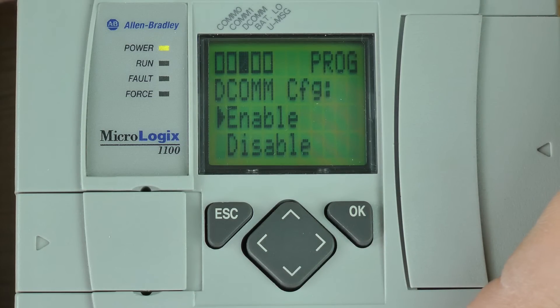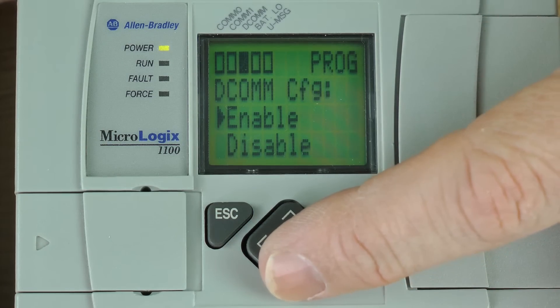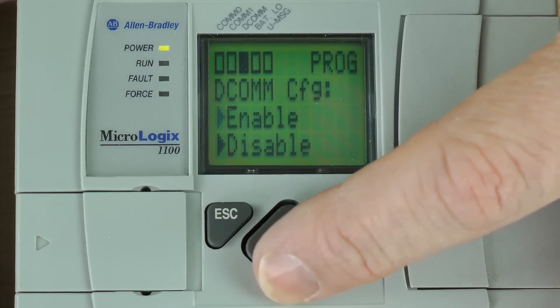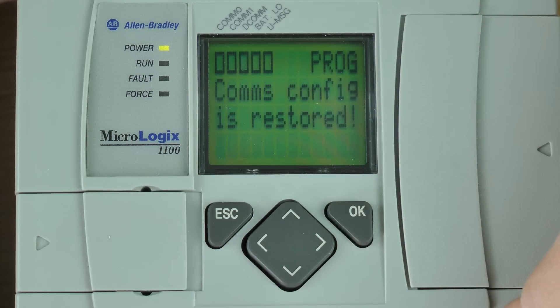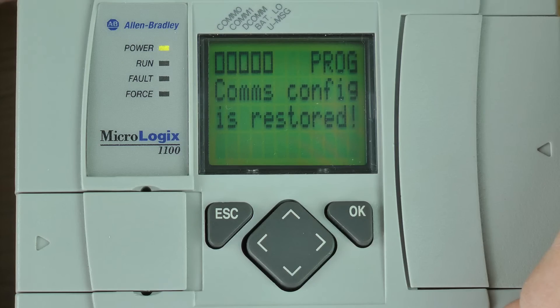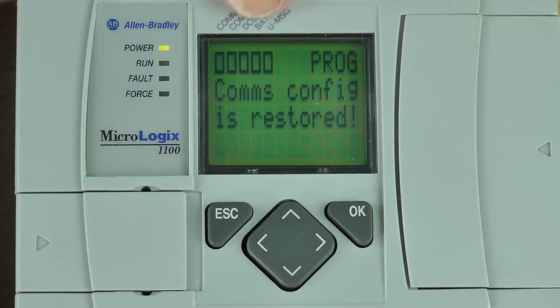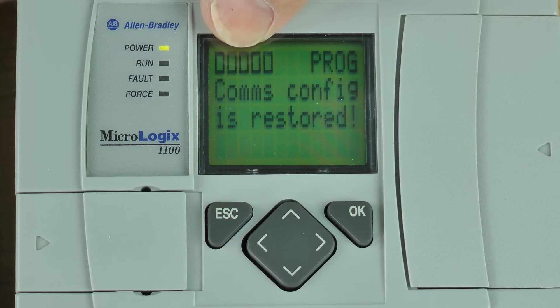I'm going to press the down arrow button once and okay to disable DCOM. Now you see a message saying comms config is restored. You'll also notice the middle square at the top of the screen is now hollow again, indicating that DCOM has been turned off.